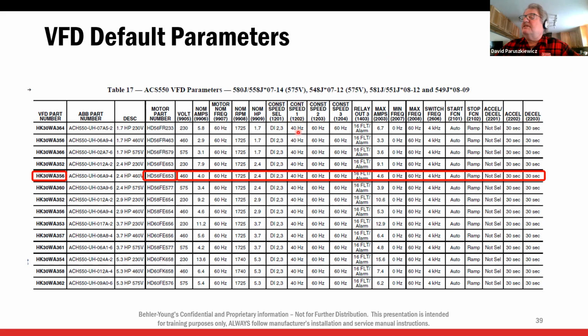So constant speed 1 low is 40 hertz, constant speed 2 is 60 hertz. These are both set low from the factory. And then max amps, this is a really important one, because if the unit's drawing more than what this max amps are set at, the motor's not going to run at full speed either. Minimum frequency, 0. If that's anything else but 0, that means the drive won't shut the blower off completely. And so on. So just basically follow those.